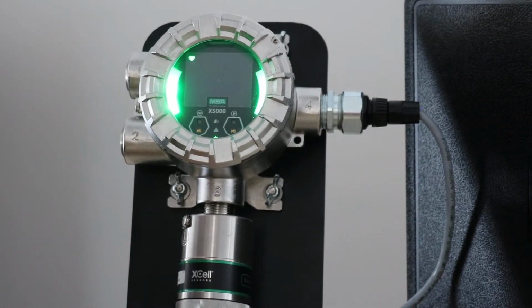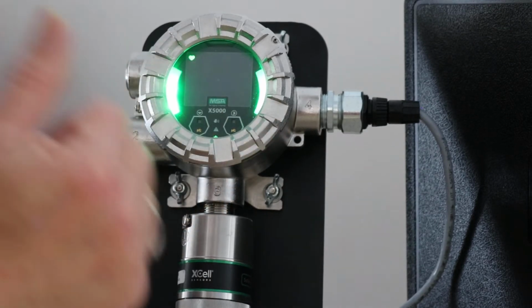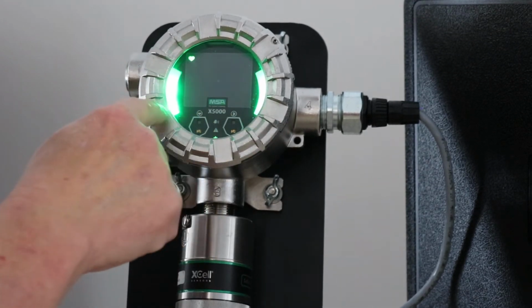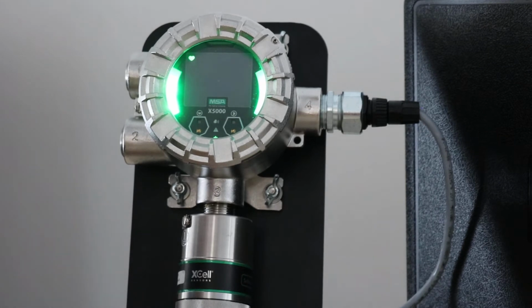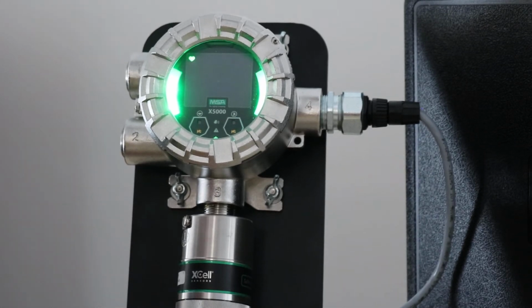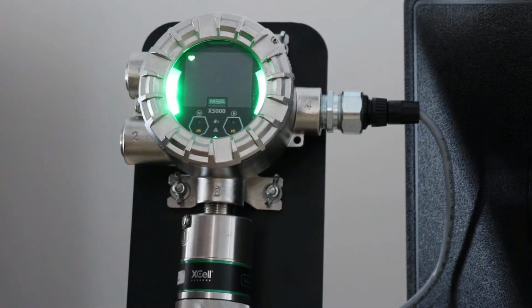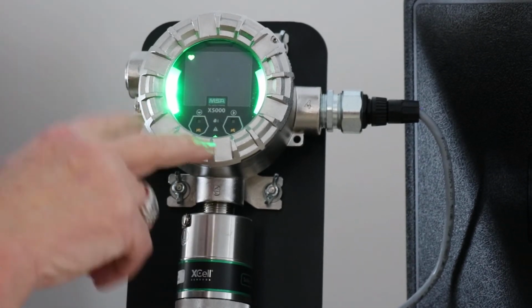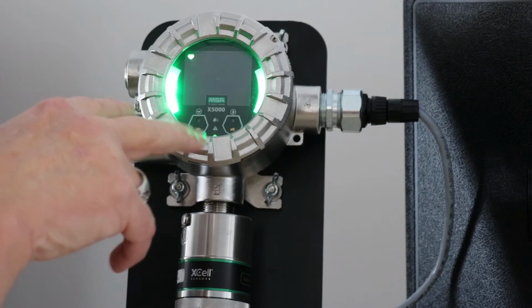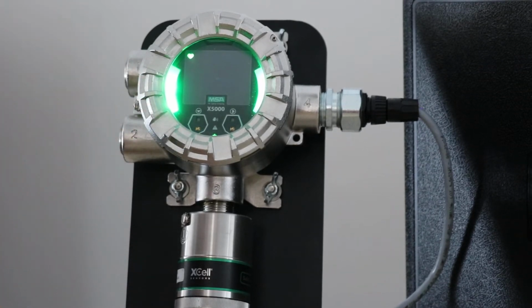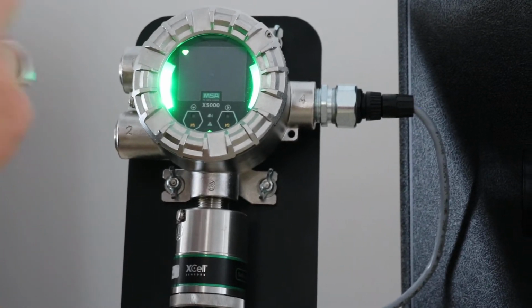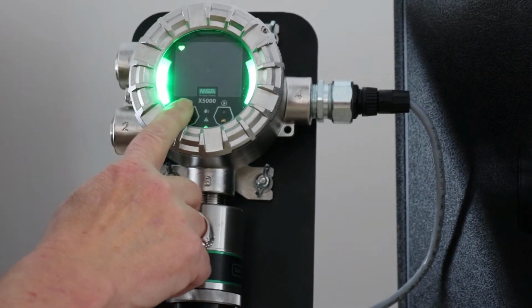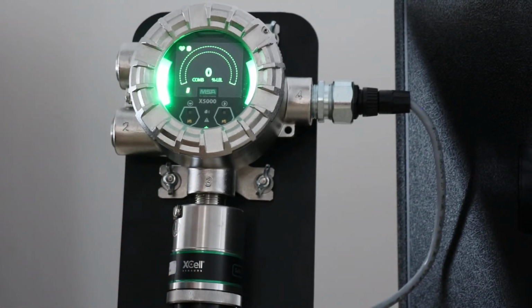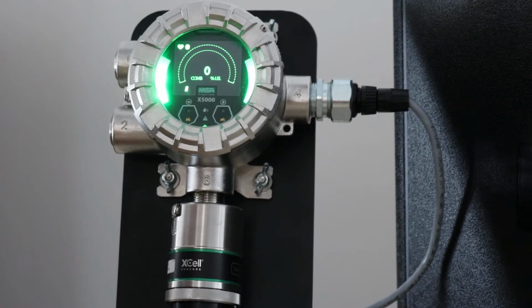Okay? If anything changes along the way, if it goes into an alarm, these LEDs will turn red, the display will come on. If it goes into fault, these LEDs will turn yellow and also light up the display. Even if it doesn't go in alarm or fault, if the gas level changes, it will light up the display. So with that, I will light up the display by simply pressing this. Wakes it up. As you can see, it says 0% LEL combustible.